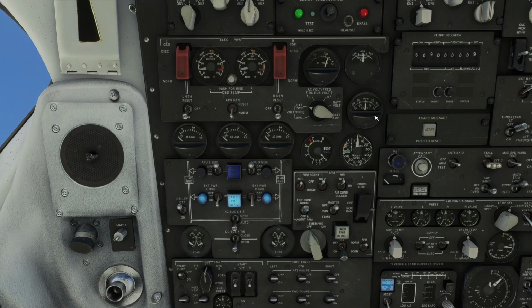So those are AC gauges. Down here are our volts and amps for the DC system. If we need to see our readouts on how much amps we're drawing off the current, the only thing we won't have is a frequency on DC, because DC doesn't have a frequency. It's all direct current, it goes in one direction, doesn't change direction. So you have volts, the pressure, and the amp draw, the amount of current the system requires. The system in the aircraft is basically a 24, 25 volt system, kind of similar to your car battery which is usually 12 volts, so it's like double that - a little more high power.